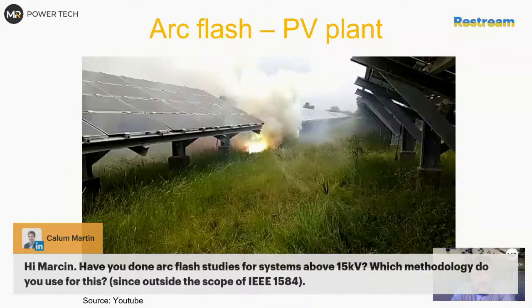So generally speaking, you can. What I do there, just for arc flash, I just change the voltage to 15 kV, just not to have the error in the software. Because if you calculate manually, you will see no big difference, actually no difference at all. But if you run it in software like SKM or ETAP, it will just tell you it's an error and immediately switch to the Lee equation or something different. So generally, I just adjust the voltage to the proper level for arc flash, and it doesn't make a huge difference. This is more for load flow.